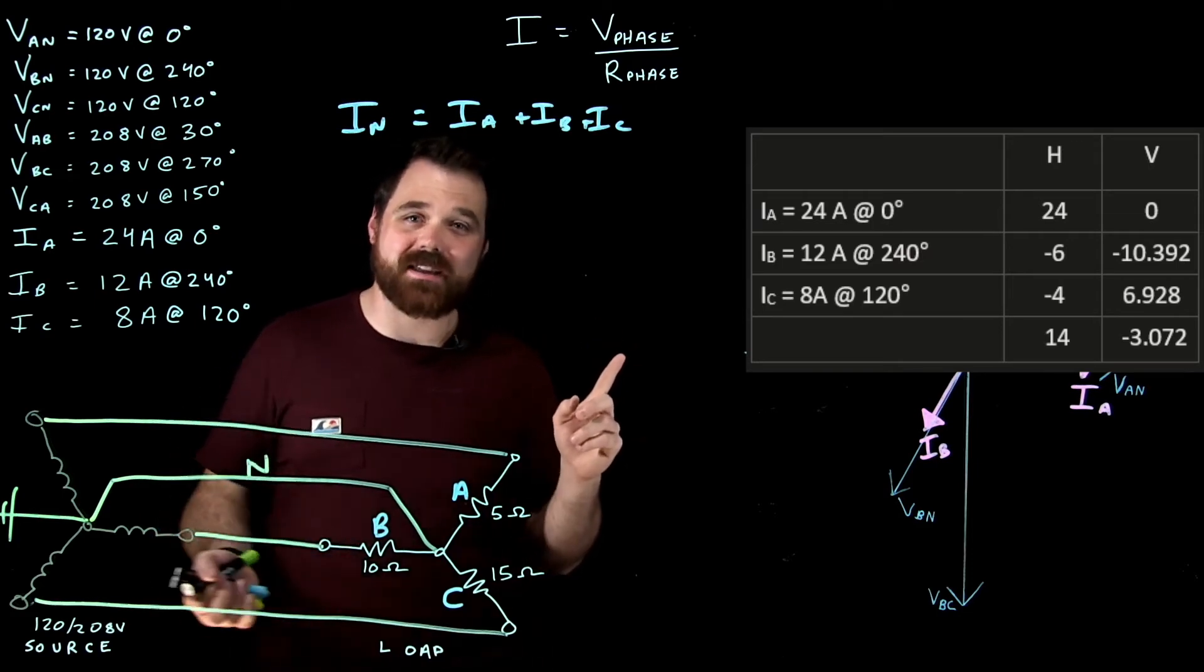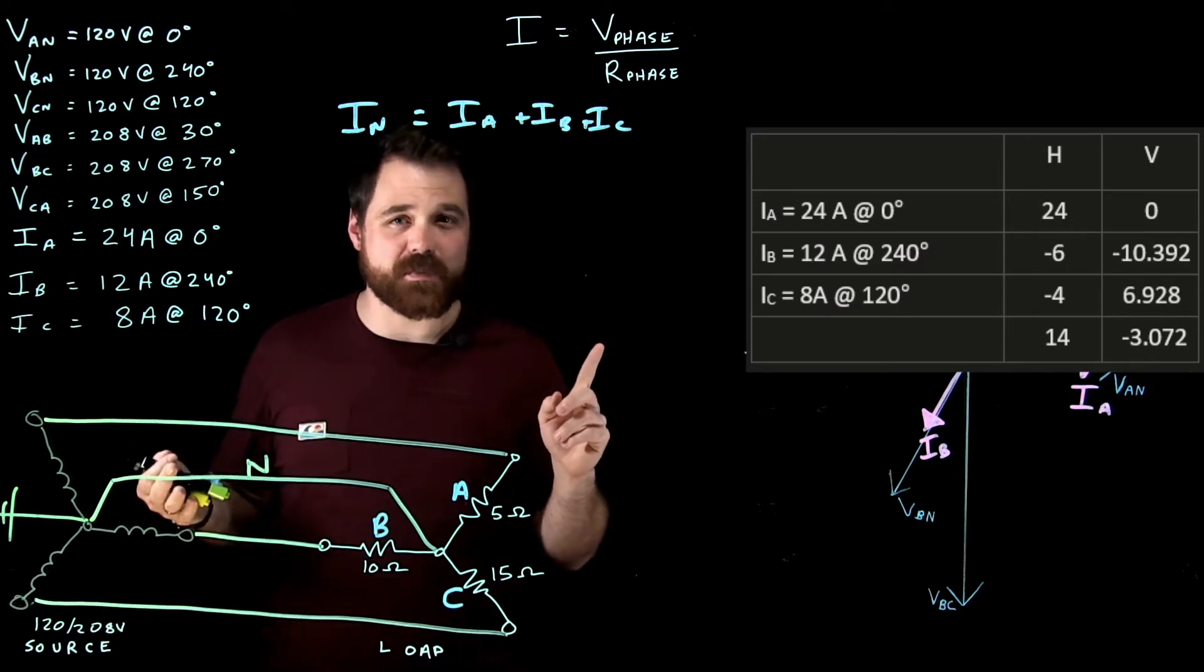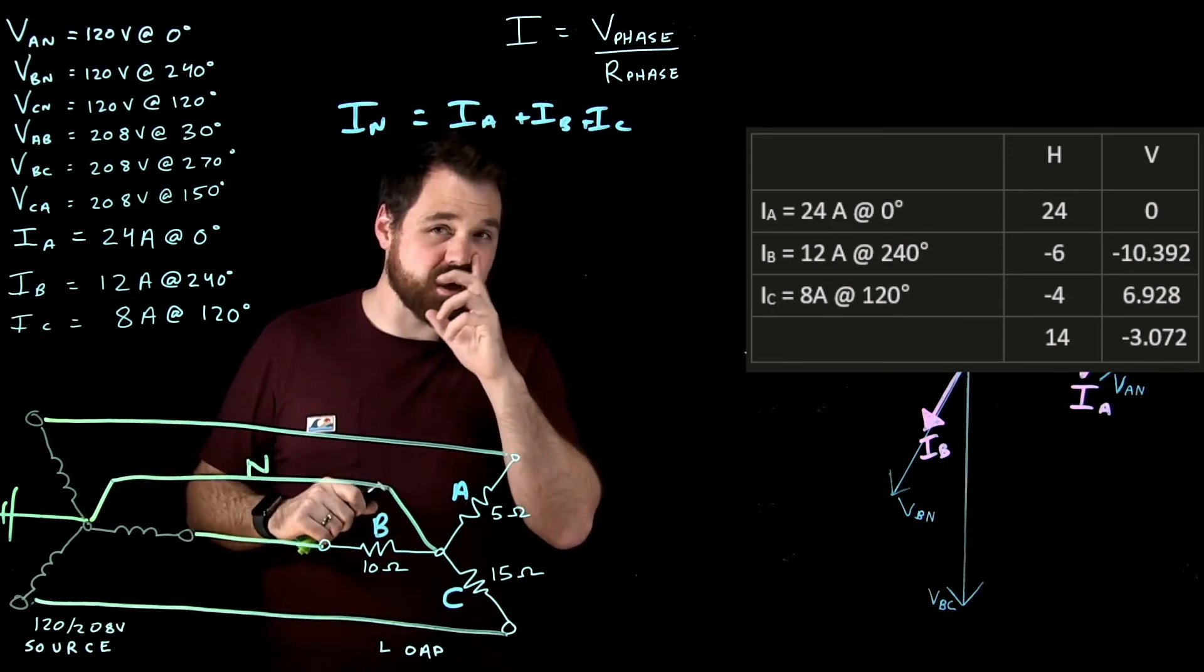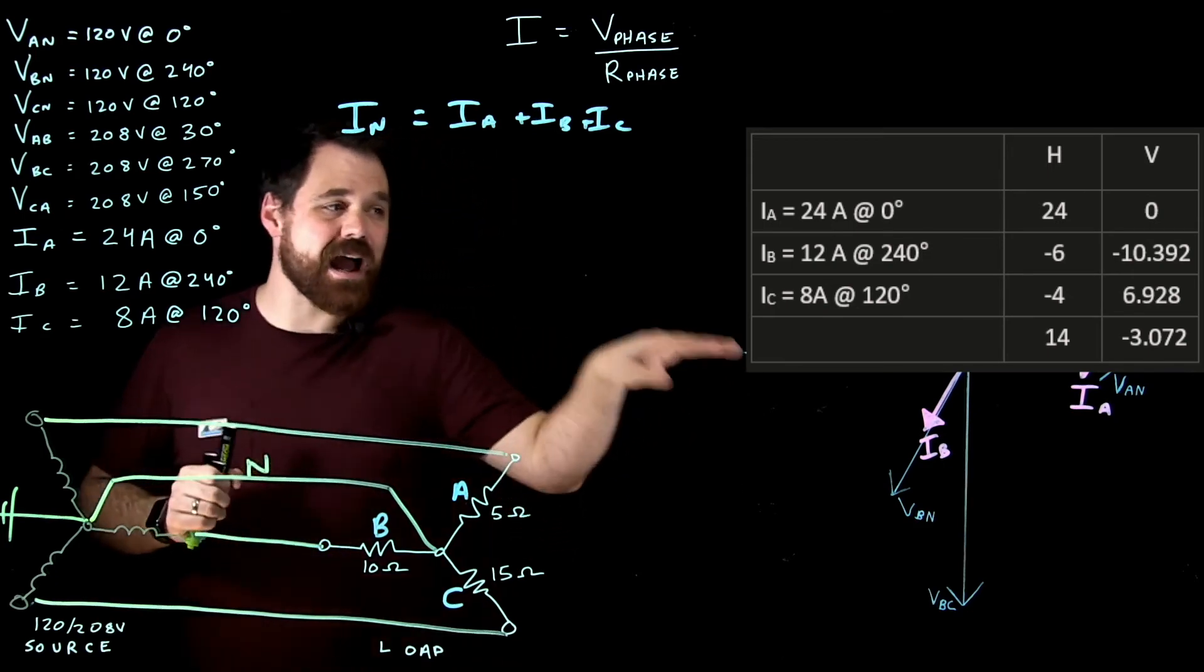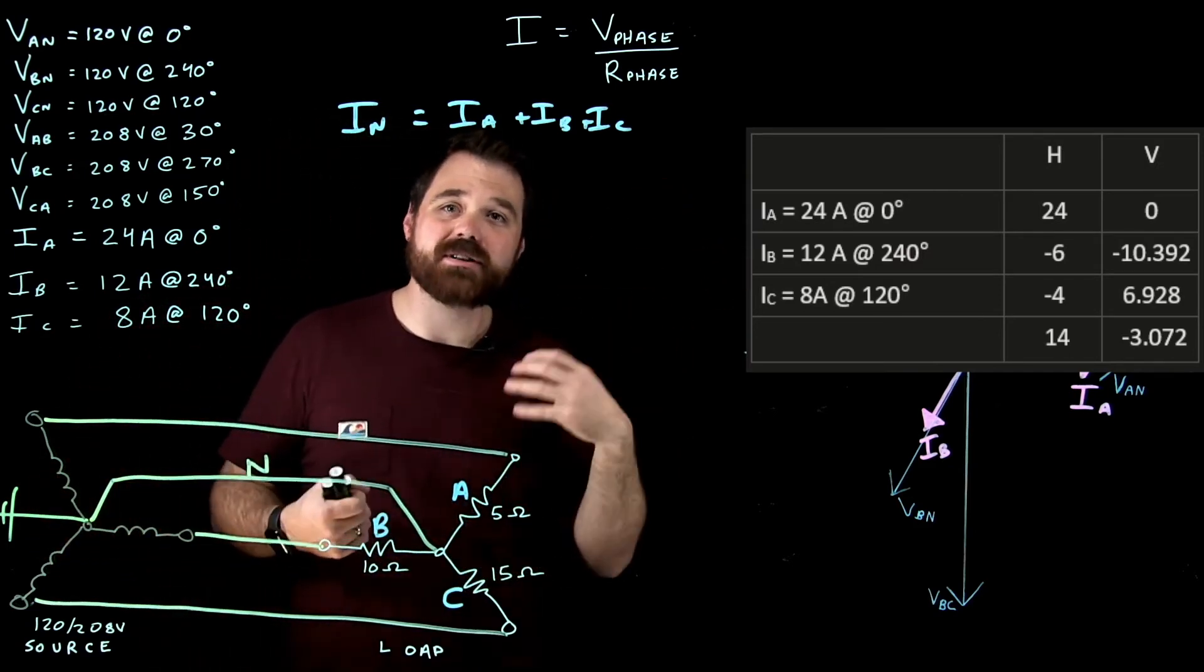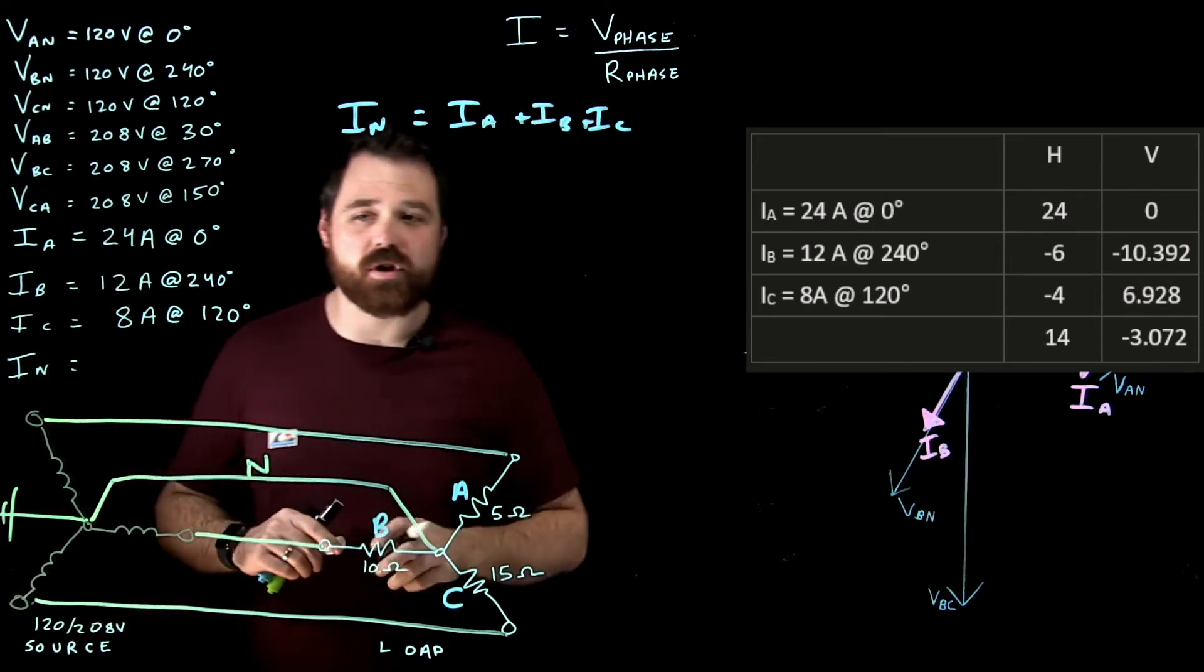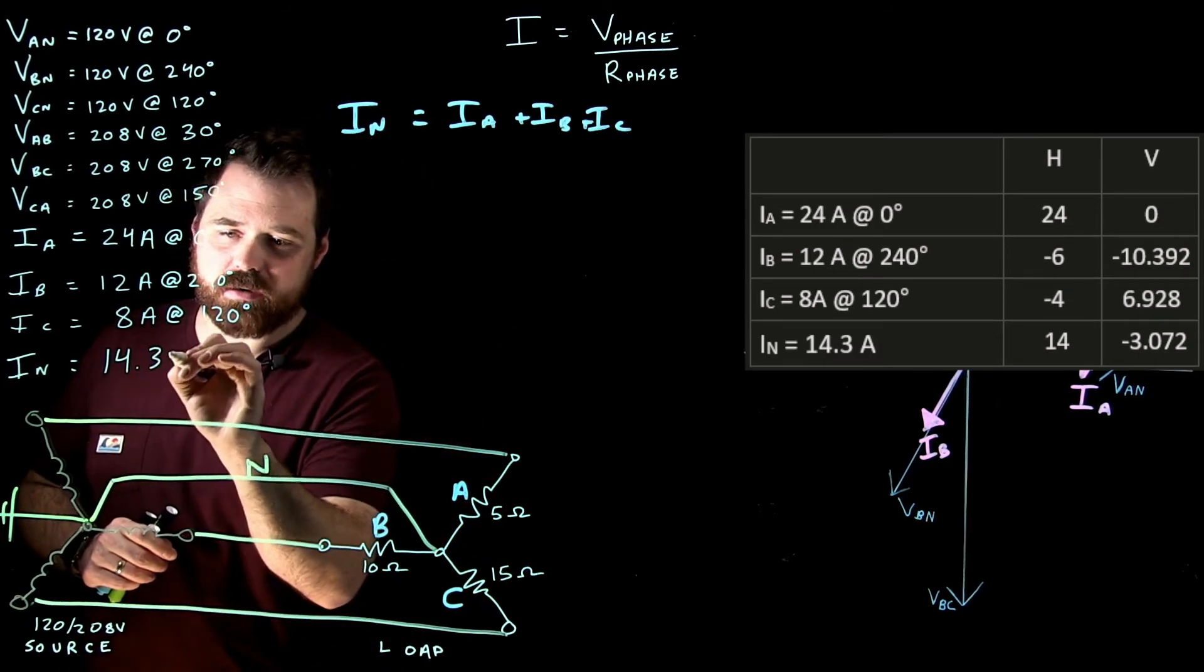Now, I take that chart, and I take that information. I've got a positive 14 as my horizontal, and a negative 3.072 as my vertical, which tells me that when I go back to my phasor diagram, that's going to be down, over, and then down. Now, I use those two numbers, I do Pythagorean's theorem, and I end up with a neutral current. And that neutral current is 14.3 amps.